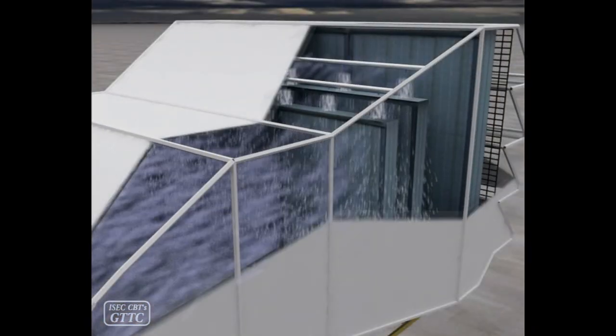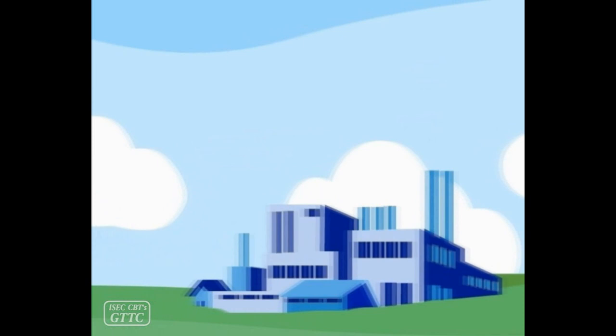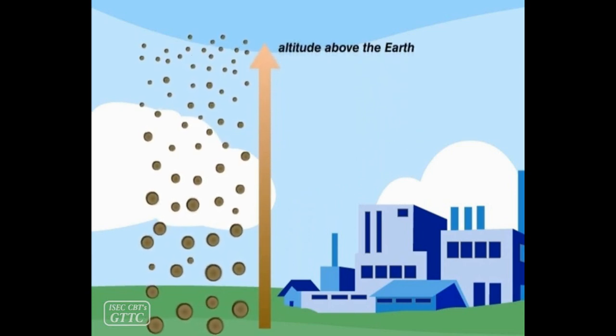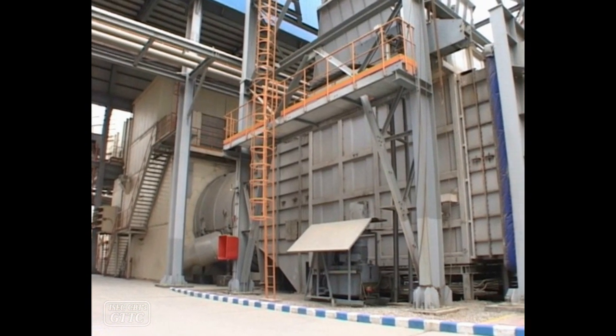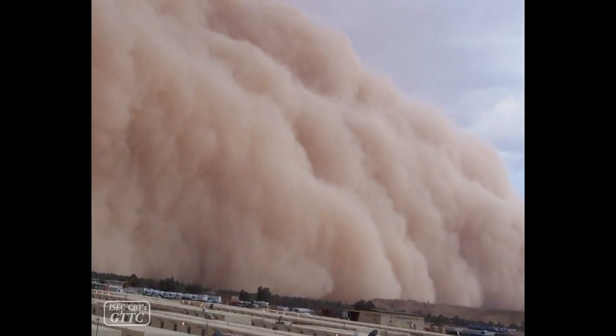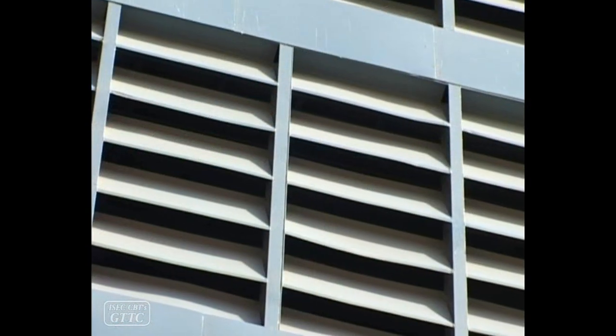The air needed for the gas turbine must be completely clean and free of suspended particles. The diameter of these particles reduces with the increase of altitude. The presence of these particles in the inlet air causes many problems when passing through different sections of the gas turbine. In stormy weather, huge amounts of dust are dispersed in the ambient environment, and the amount of these particles increases severely.